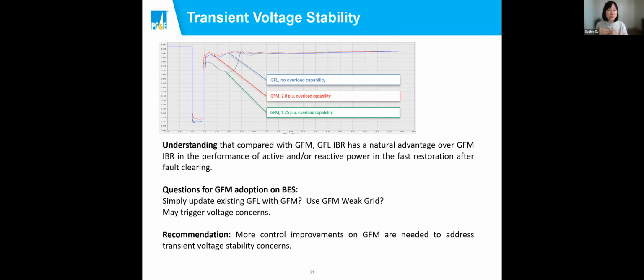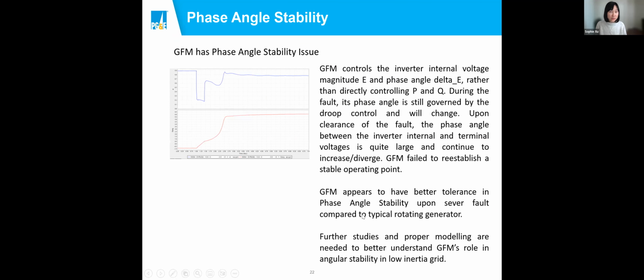And I think local voltage issues could be the starting point if we think about adopting the grid forming inverter by need, because that could happen sooner than frequency stability issues or any additional need to stabilize angular stability issues on the grid. Potentially, we can recommend adding additional controls to address this. I've been talking to Wei, and I think he's working on some potential solutions. If there's additional control or any way that we can address this kind of voltage control, then I think grid forming inverters can be adopted much sooner.